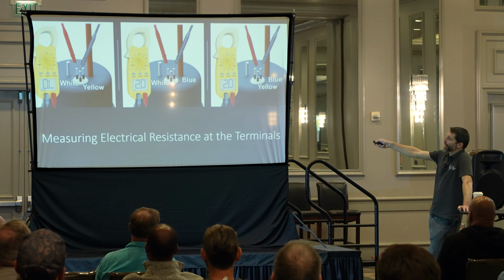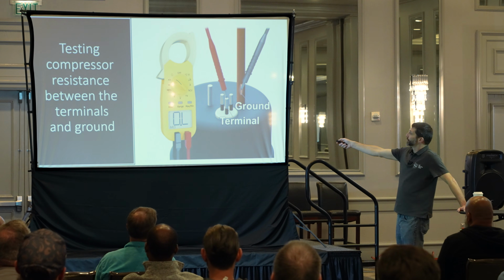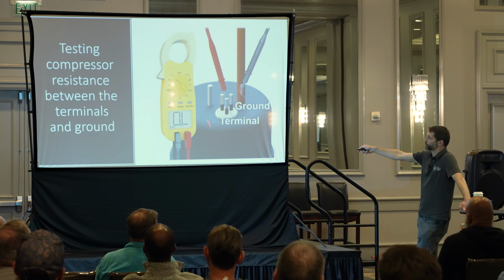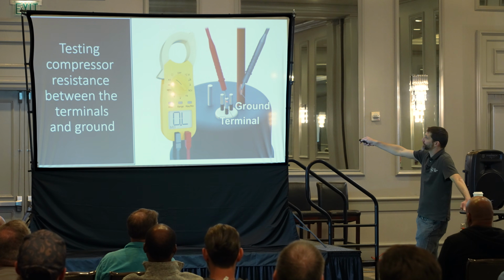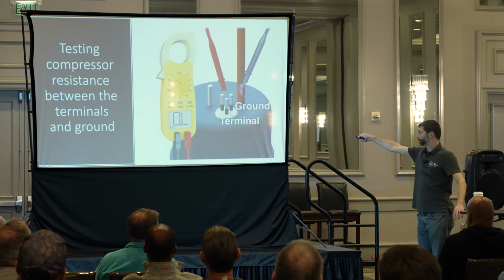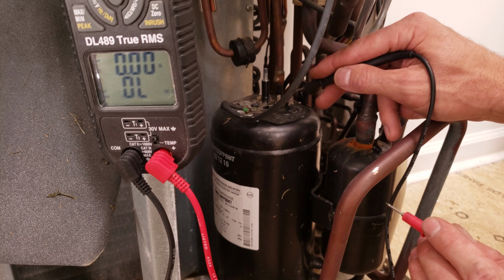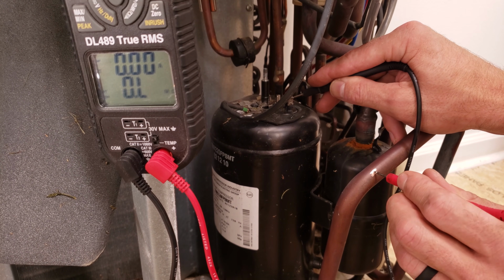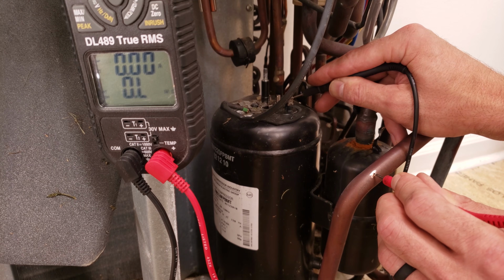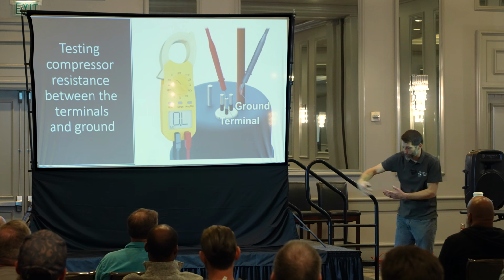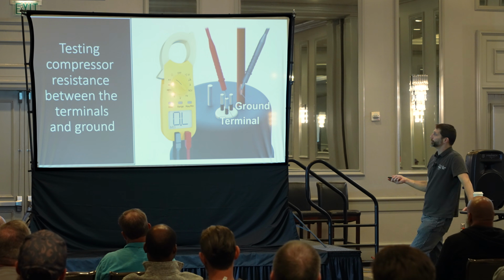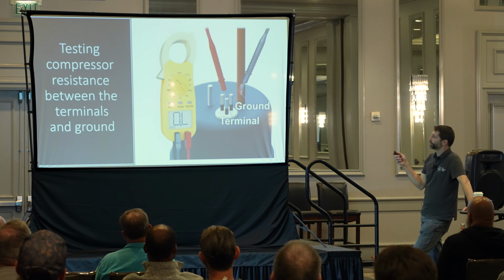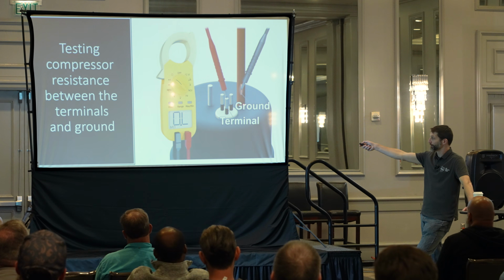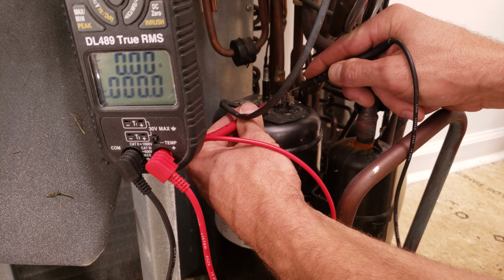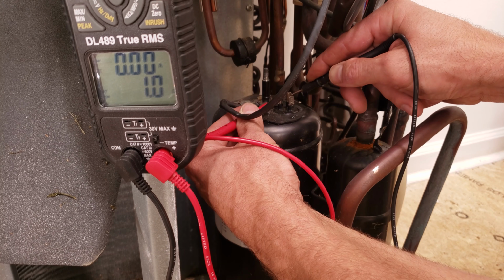And that means that that compressor is no longer electrically good. Likewise, if you have any type of electrical resistance whatsoever on your multimeter when you measure from one of the tabs or the wires to the ground, they call it a scratch test or whatever, onto the frame here or just right onto the copper, you know you have a problem. One of the windings has shorted up against the ground frame of the compressor. That's how you tell electrically if it's intact. You should be reading OL when you test the ground. You should be getting a matching electrical resistance when you test between all 3 pairs.